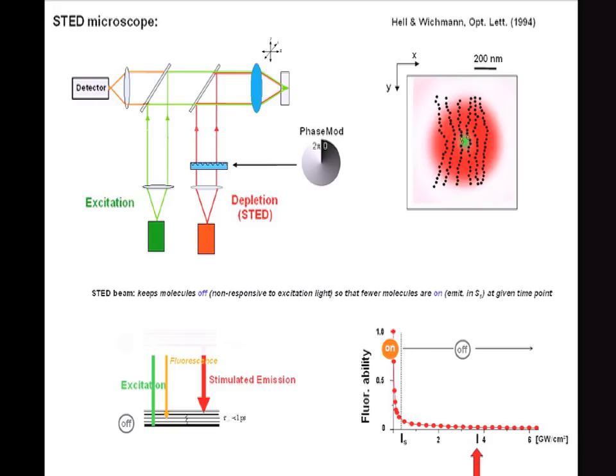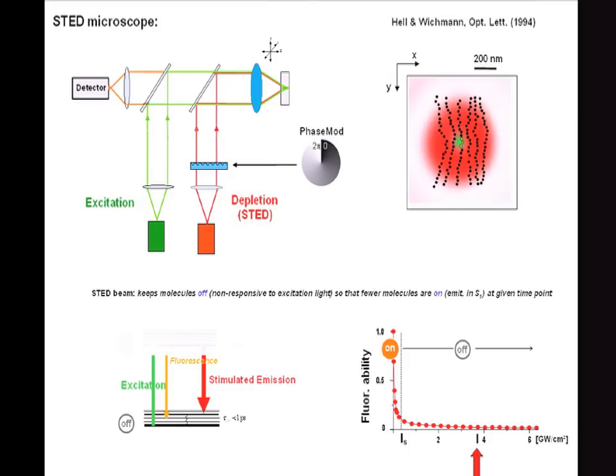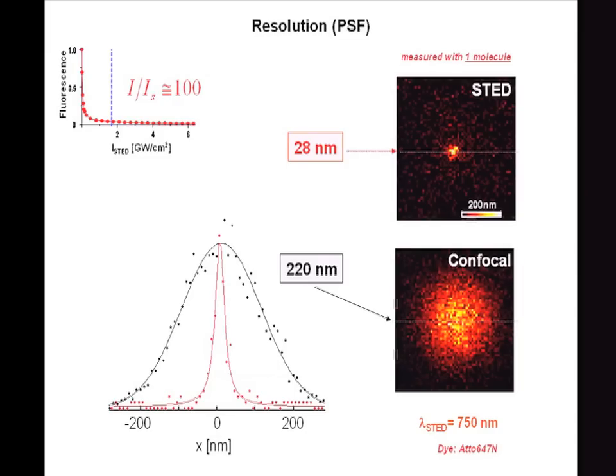This is exactly how we break the diffraction barrier. The resolution will be given by the size of that small region in which fluorescence is still allowed, and that size can be very small. Here we have a diameter of about 220 nanometers for a normal confocal microscope, and then 28 nanometers for the STED case, measured with a probing single molecule which was scanned through the focal region. If that region has become so small, we must be able to see much sharper than before.